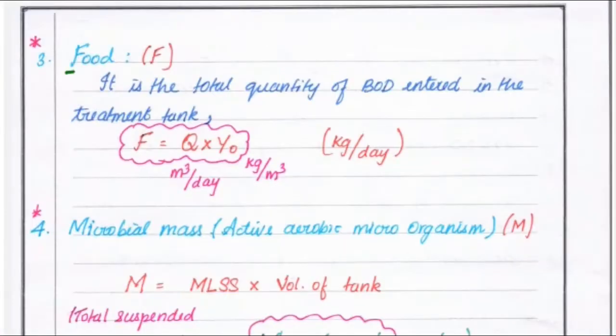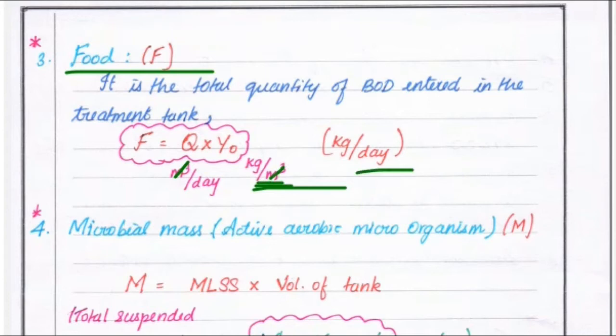The third parameter is food, F — the total quantity of BOD entered in the treatment tank. F equals Q into Y-naught, where Q is in meter cube per day and Y-naught is in kg per meter cube. The meter cube units cancel, so the unit of F is kg per day.